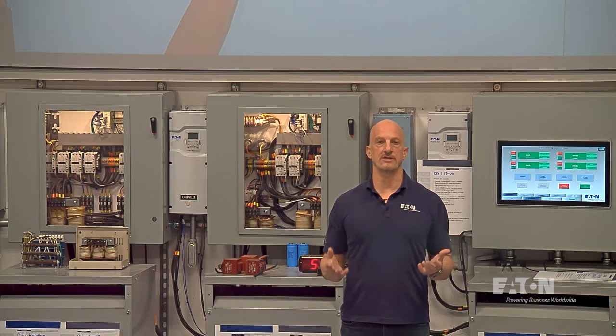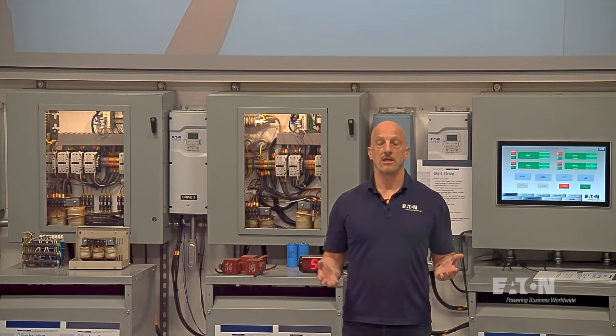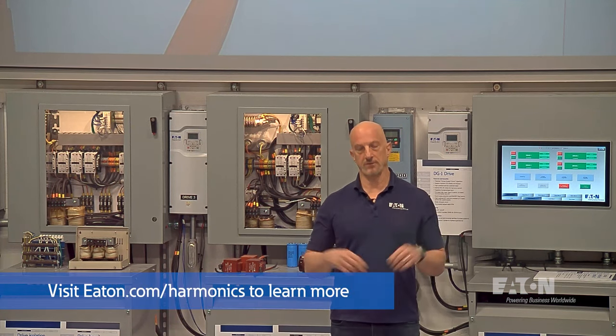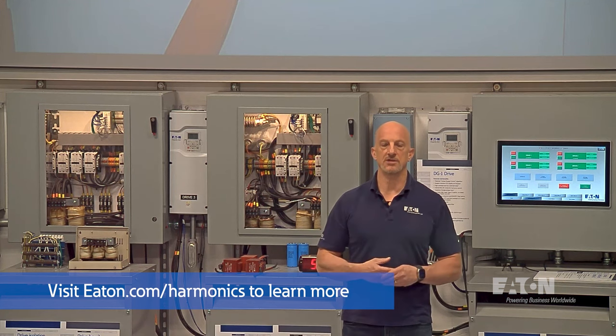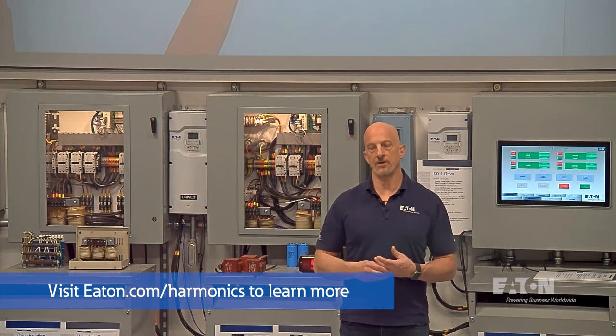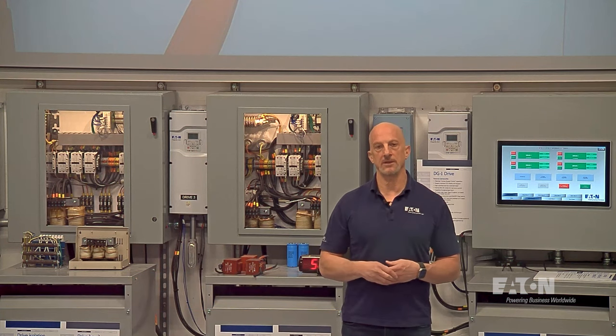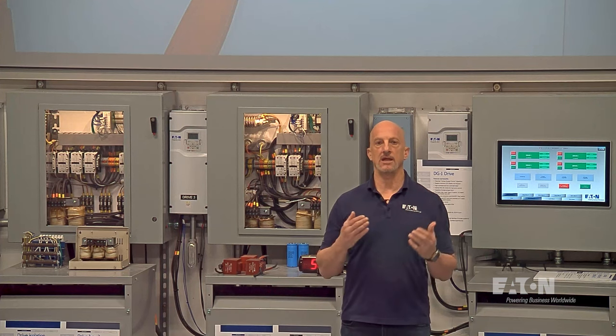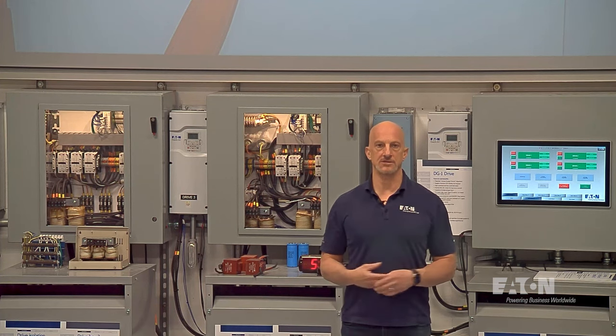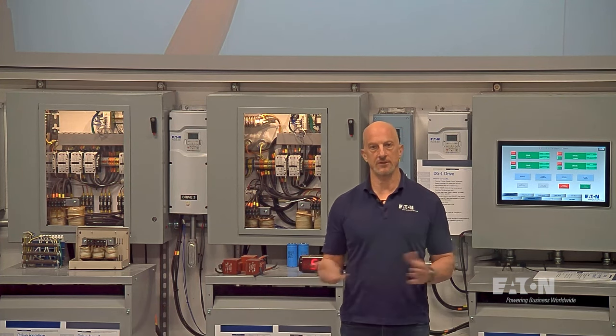High frequency filters, which are going to be in the kilohertz range, which are basically surge protection, they work in that upper frequency range. You do want to force that away from the equipment. But that's, again, that's a different animal than a fundamental harmonic filter for power system harmonics like third, fifth, seventh, and so forth.